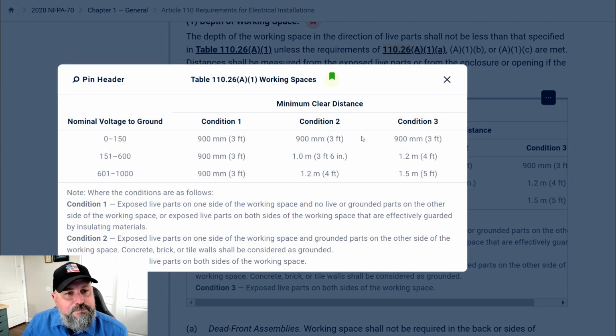So let's see. Here's the table. So nominal voltage to ground, condition 1, condition 2, condition 3. So 0 to 150 volts is going to be condition 1, 3 feet. Let's go into the conditions actually first. Condition 1: exposed live parts on one side of the working space and no live or grounded parts on the other side of the working space, or exposed live parts on both sides of the working space that are effectively guarded by insulating materials. So that's condition 1.